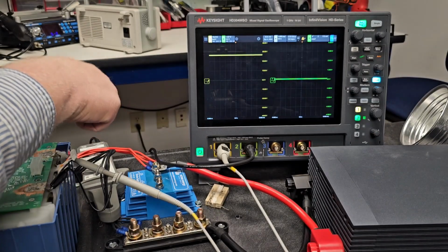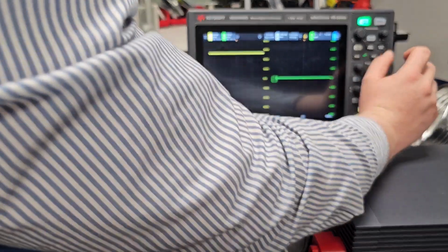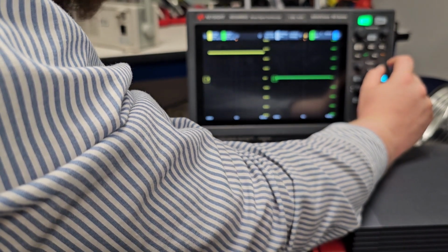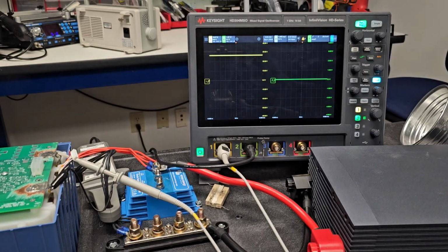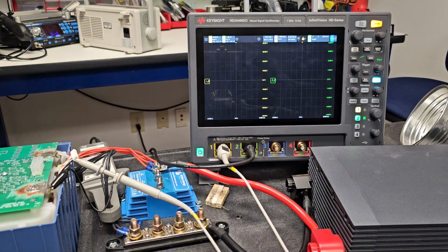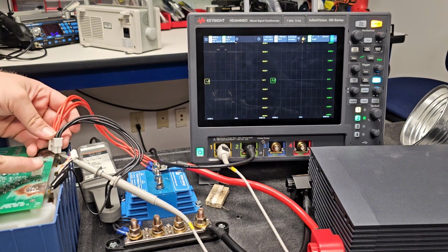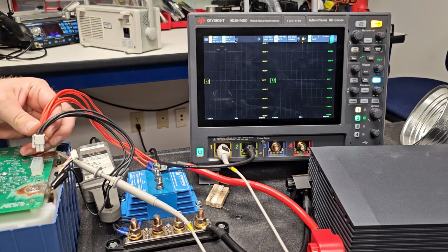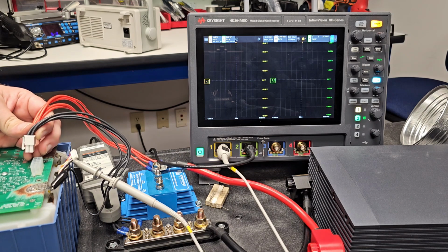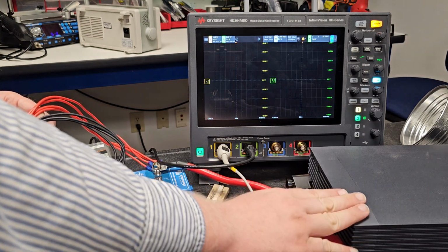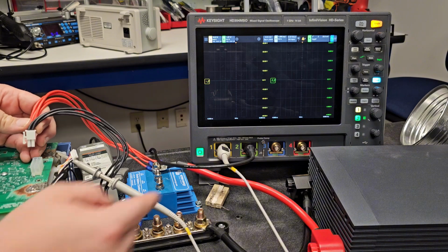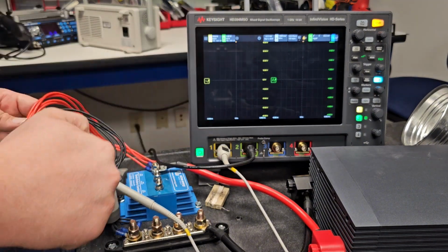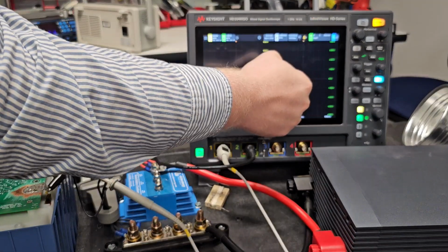Here's my trigger. So this is measuring at 10 millivolts per amp. I'm expecting this to be around 150, so I just want to set this, I don't know, 25 millivolts. 25 millivolts will be fine. So I'm going to set this to a single trigger. And if you watch closely here around this point, you'll see an arc. And that arc is what is charging up those input capacitors for this inverter. And that is what we want to capture. We want to capture the voltage dip of the output of the battery, and we want to catch the current spike coming out of the battery.